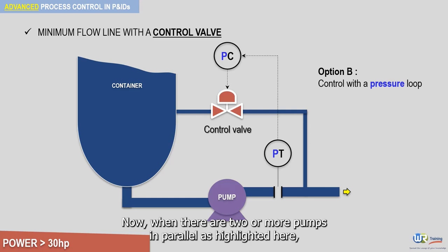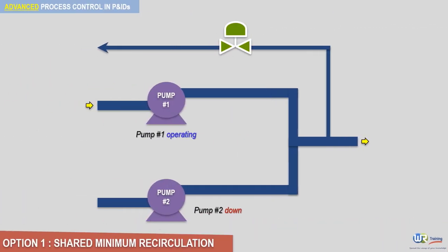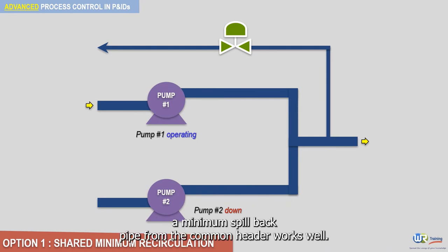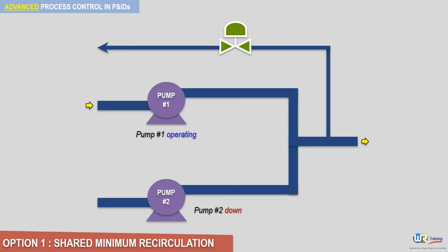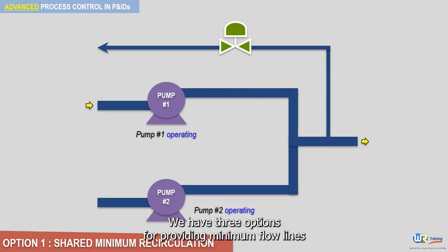When there are two or more pumps in parallel, and only one of them is operating and the rest are spares, a minimum spillback pipe from the common header works well. The question is what the minimum flow should be when there are parallel operating pumps.